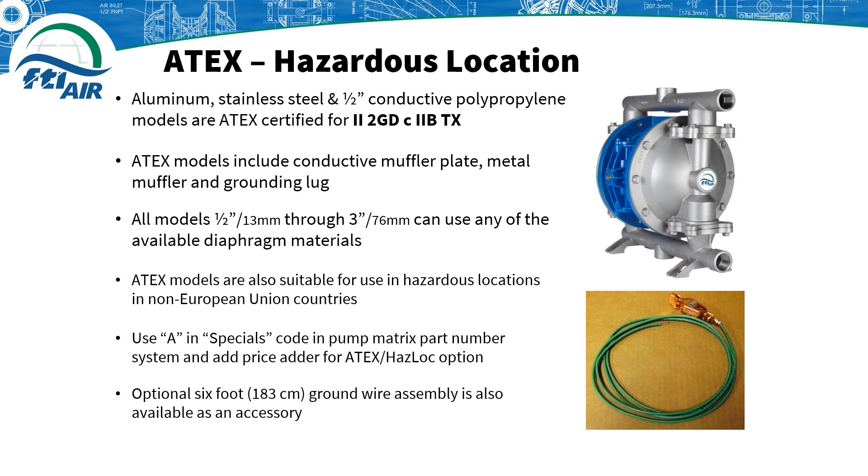Anytime you are pumping something that is flammable or if the pump is located in a dangerous area, choose one of our aluminum, stainless steel, and conductive polypropylene models that are ATEX certified. ATEX certification is for II 2GD c IIB TX. These pumps include a conductive muffler plate, a metal muffler, and a grounding lug on the pump.